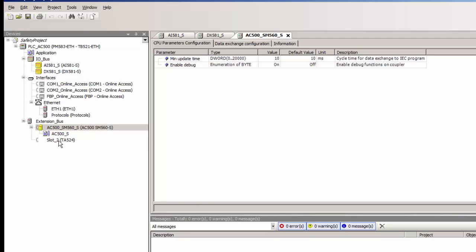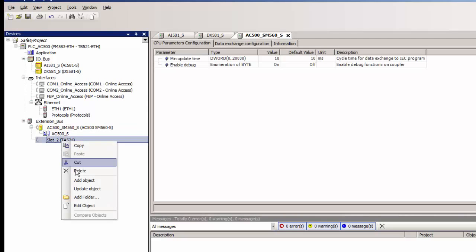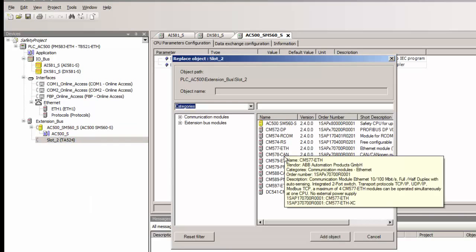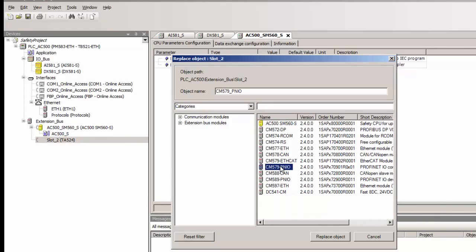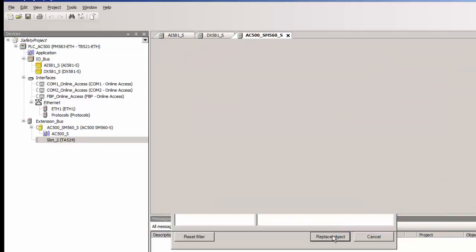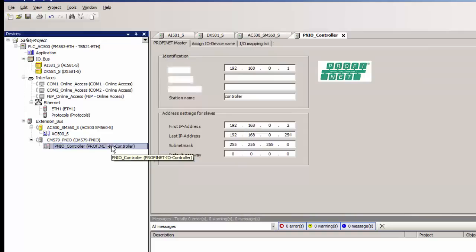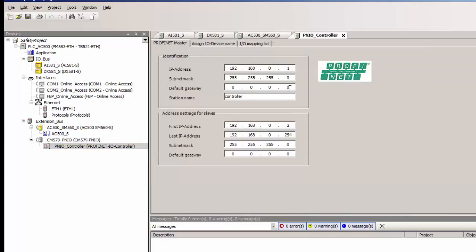Next step is to add the Profinet IO controller module CM579PNIO, which would facilitate communication between the safety CPU and the remote safety IO module via the non-safety CPU. We could live with the default settings as far as the Profinet station name and IP addresses are concerned. The Profinet IO devices will be automatically assigned with IP addresses, as shown in this range, in a sequential manner. However the user could change this address should there be a need.